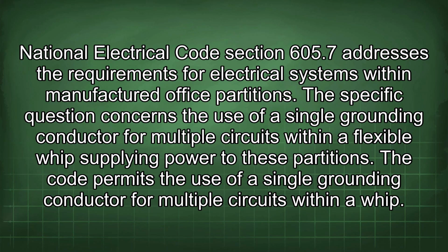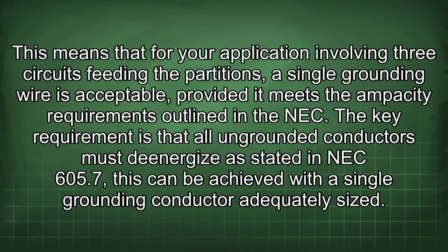National Electrical Code Section 605.7 addresses the requirements for electrical systems within manufactured office partitions. The specific question concerns the use of a single grounding conductor for multiple circuits within a flexible whip supplying power to these partitions. The code permits the use of a single grounding conductor for multiple circuits within a whip. This means that for your application involving 3 circuits feeding the partitions, a single grounding wire is acceptable, provided it meets the ampacity requirements outlined in the NEC.